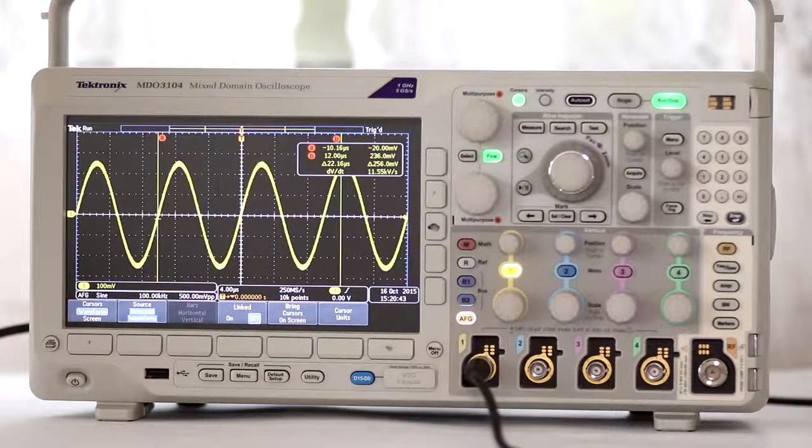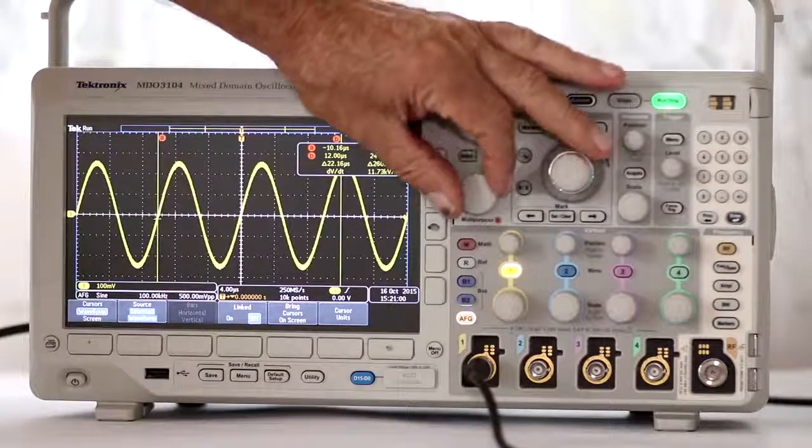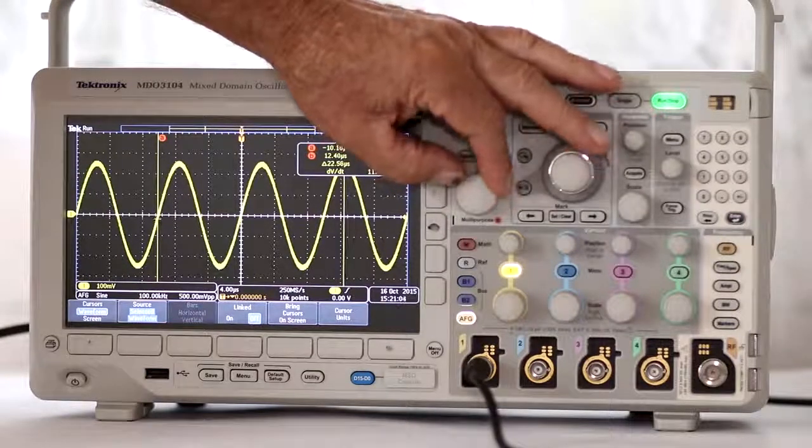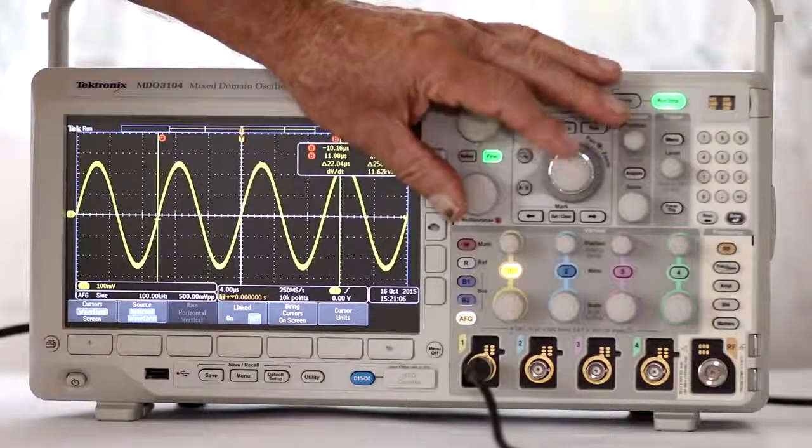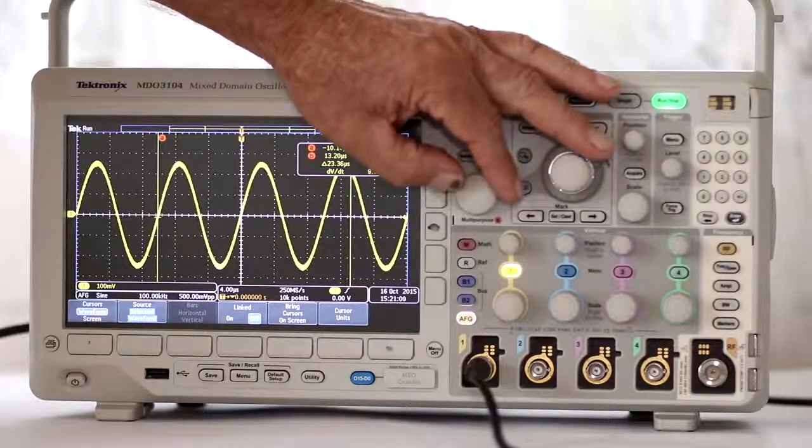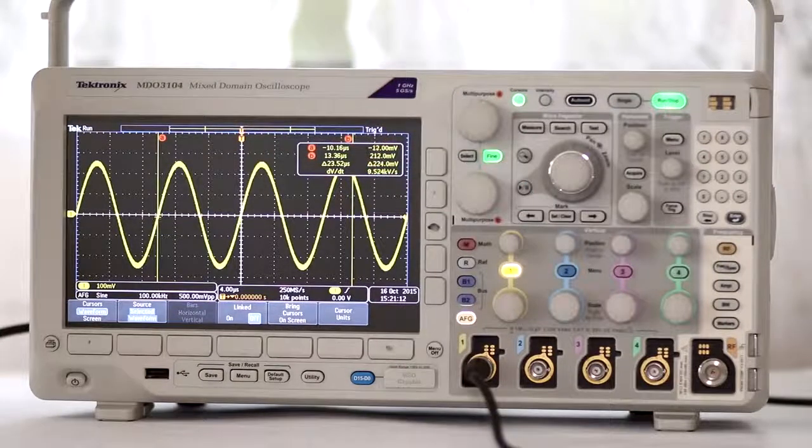The third value in the left-hand column, corresponding to the difference between the two cursors, changes as either of the two cursors is moved. This is generally the number of interest. Multipurpose knob B moves the right-hand cursor, and the values in the cursor readout window change as you would expect. The whole time, regardless of which knob is turned, the values in the right-hand column fluctuate continuously since they represent very small amounts of amplitude in the millivolt range.